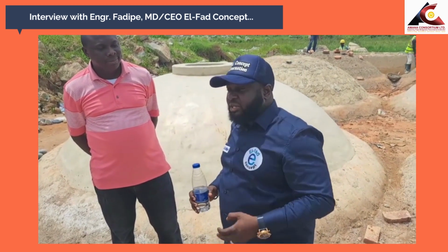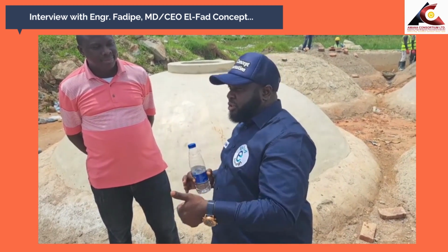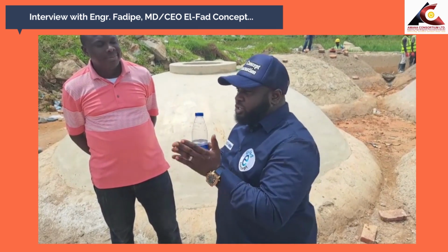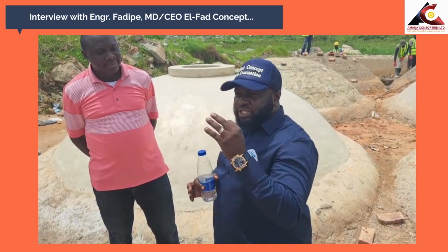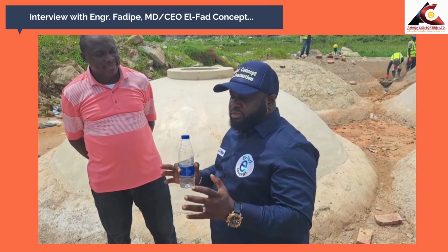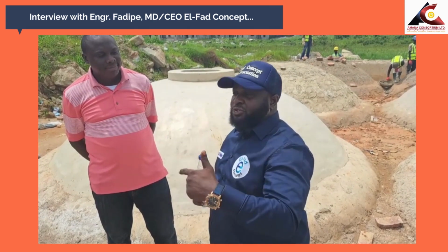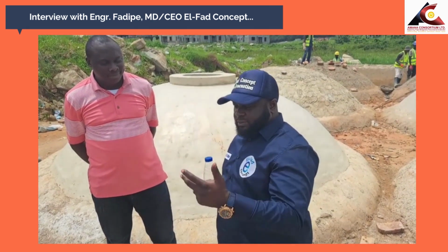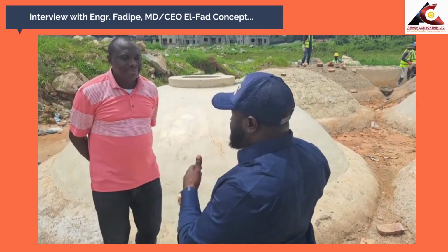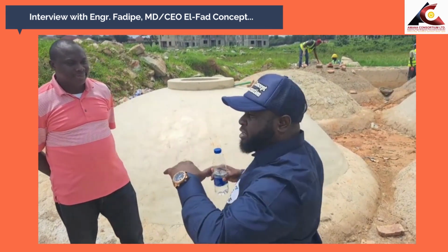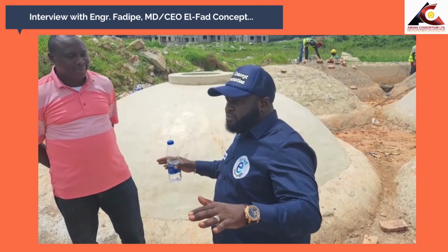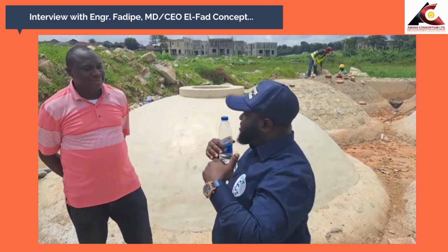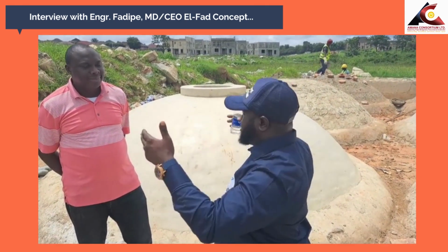So the advantage of this system is, one, there will be no more evacuation of sludge, because your sludge is what is breaking down into liquid and gas. And now there are three challenges or major issues with sewage management. One is sludge evacuation, two is odor, three is space. Now with the anaerobic fixed dome digester, because it's completely underground, this issue of space is solved. Whatever you use, you can use it back as your car park, you can use it as a green area such as this.